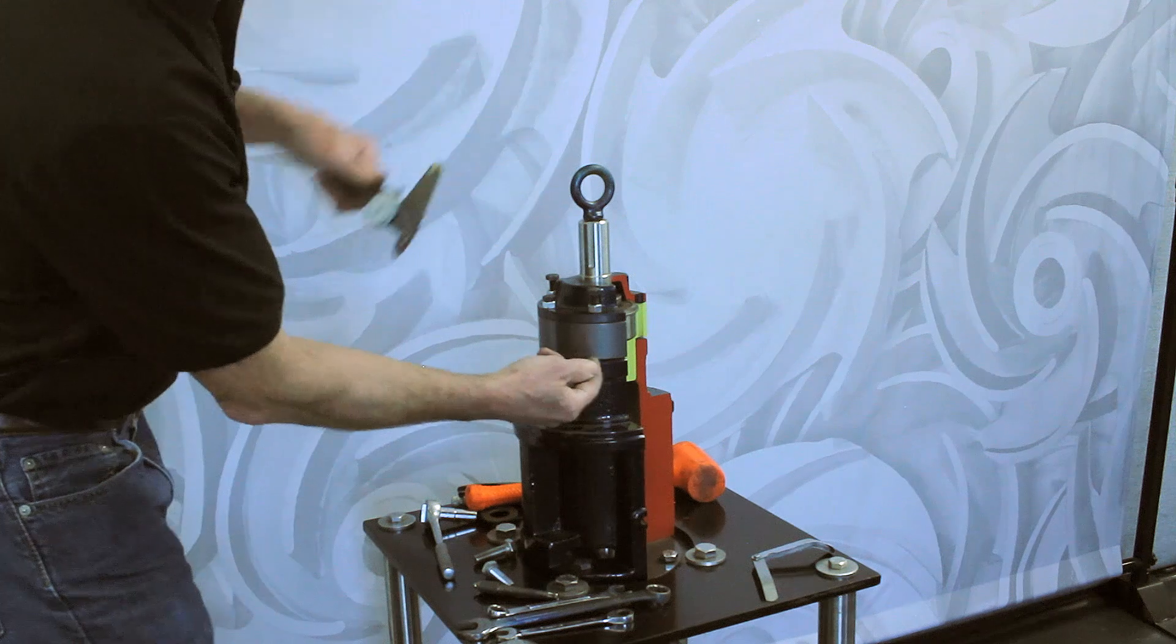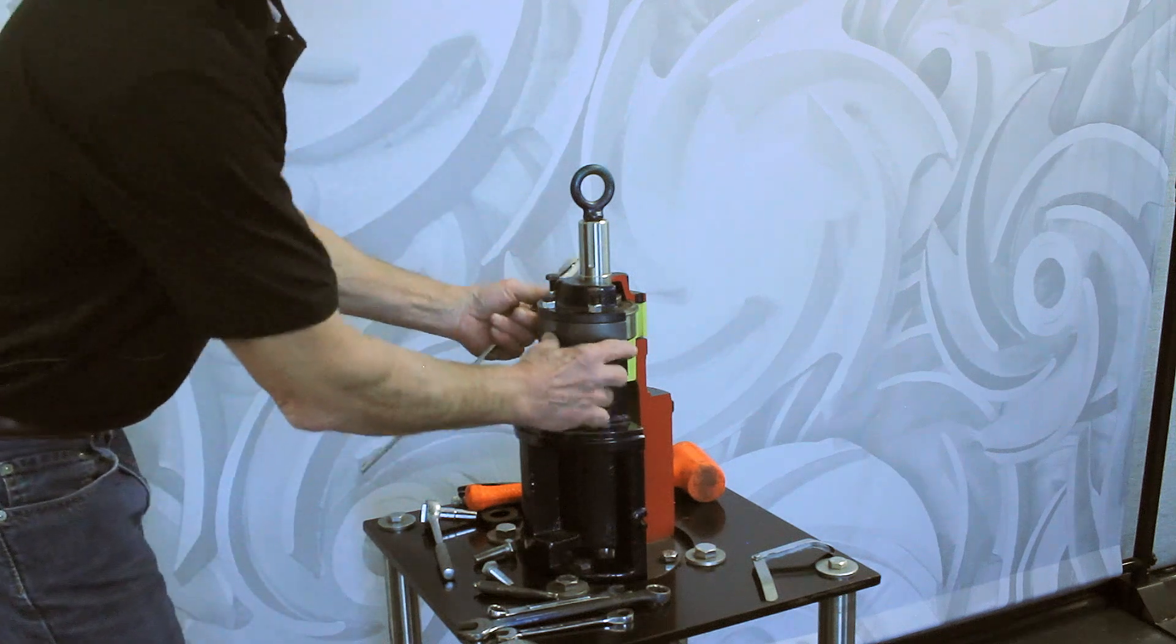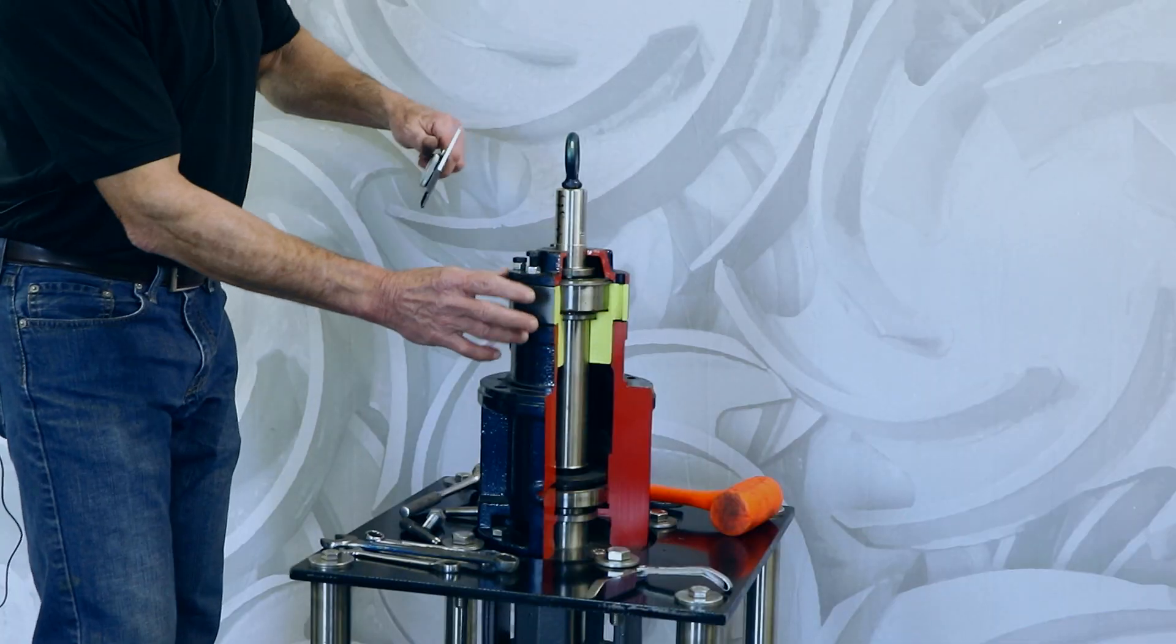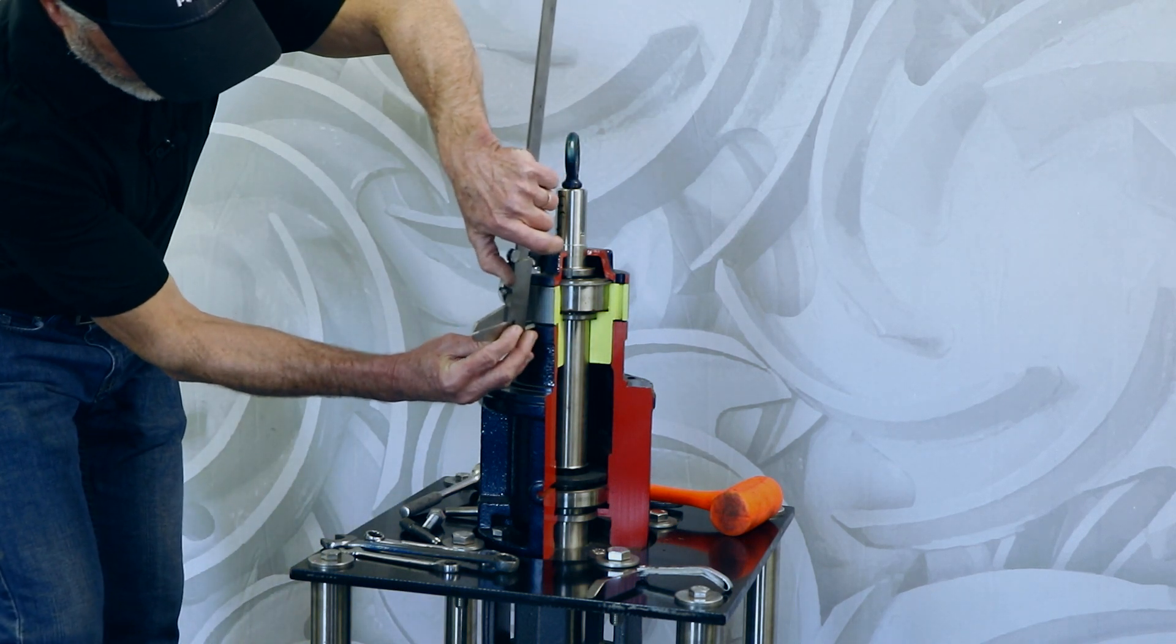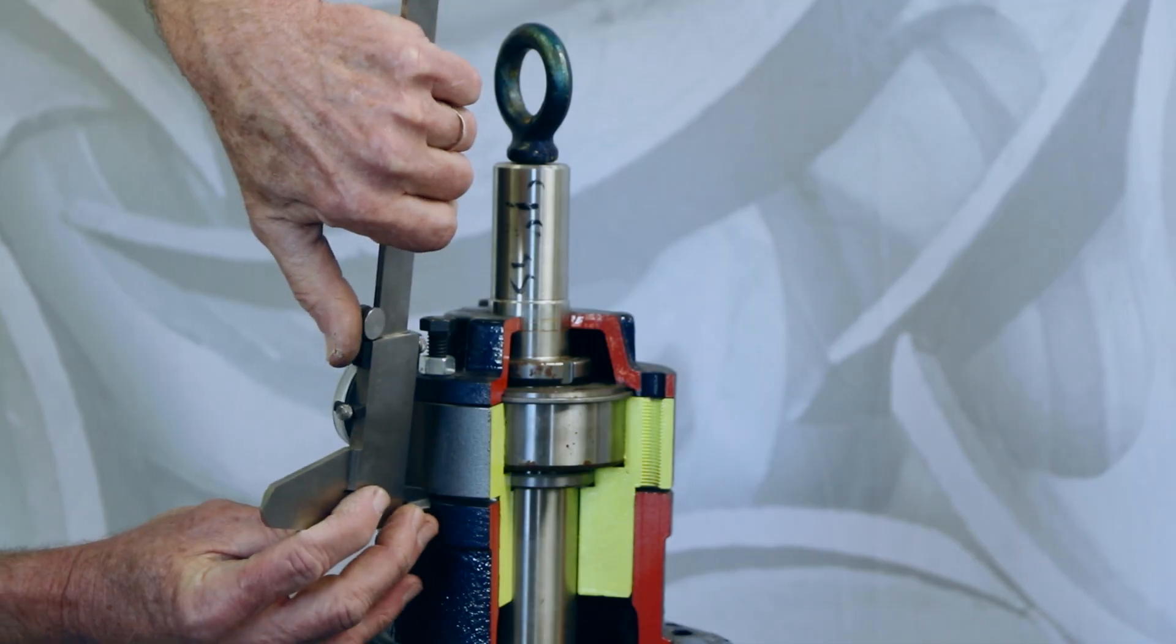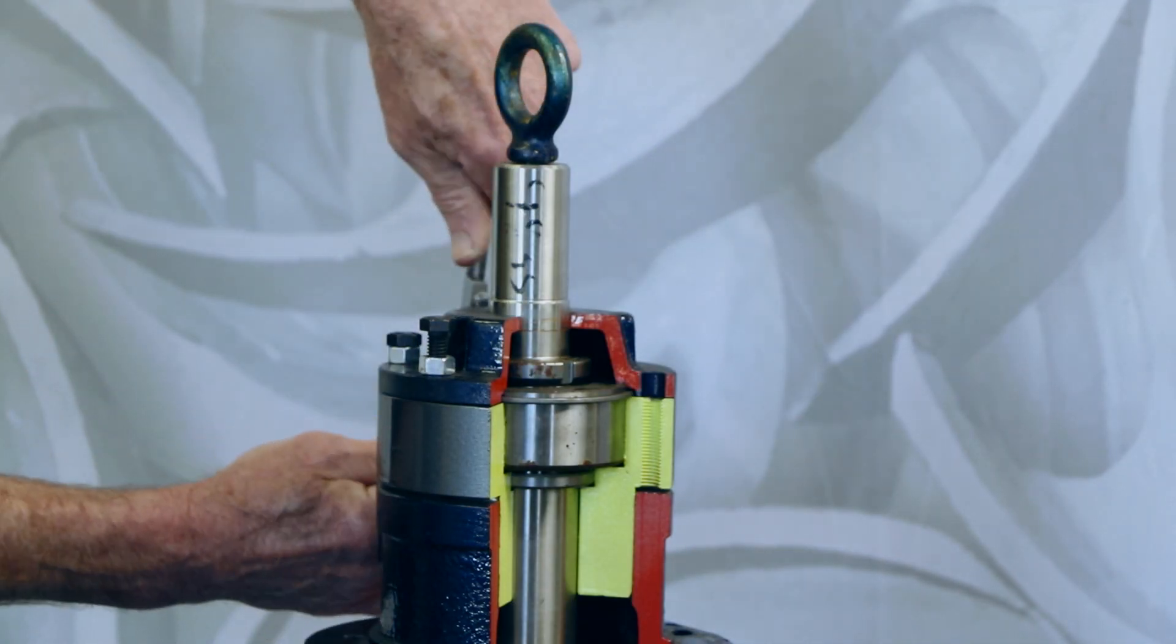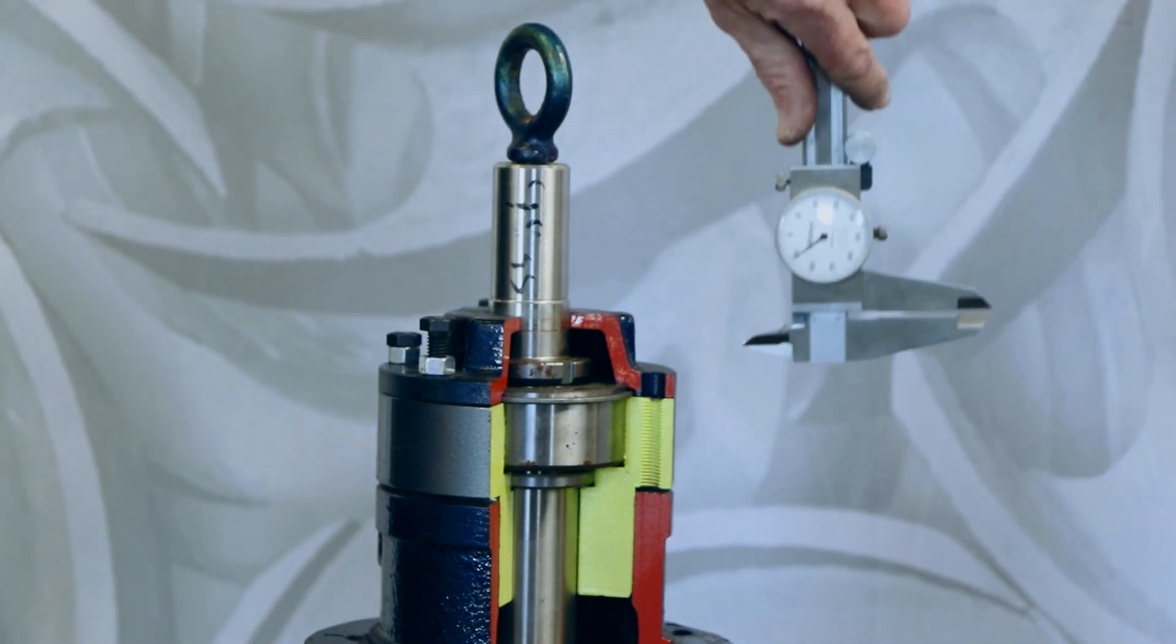One way you can check to make sure this slider is setting evenly all the way around is to take a pair of calipers and go to your three long bolts, and just out from them, check to see if you vary from one to the other.